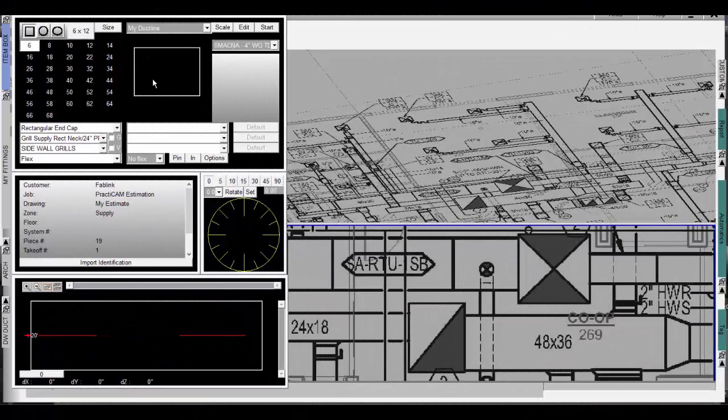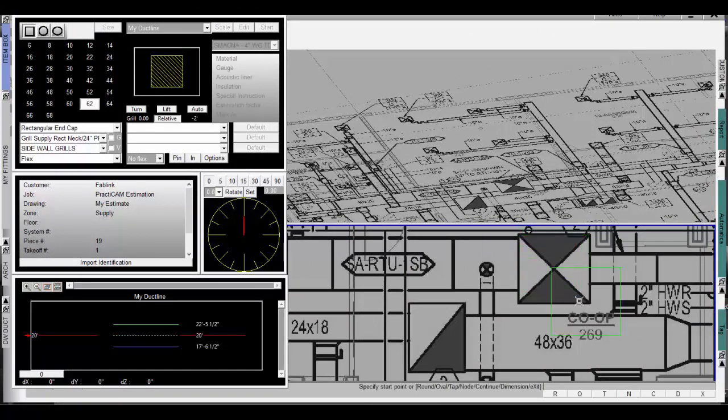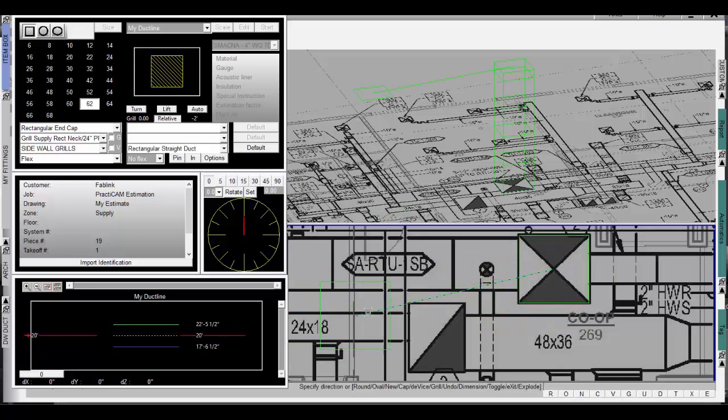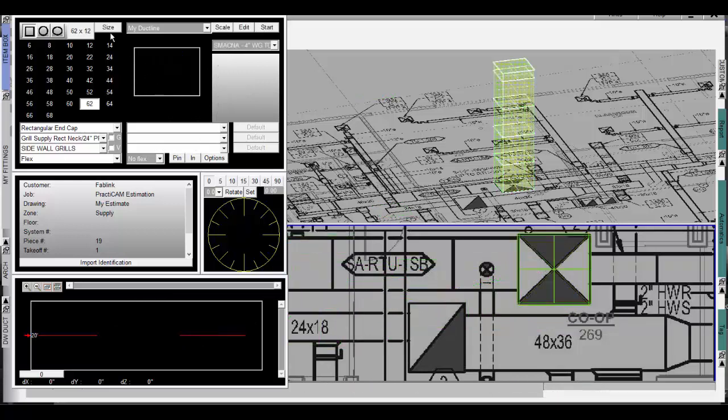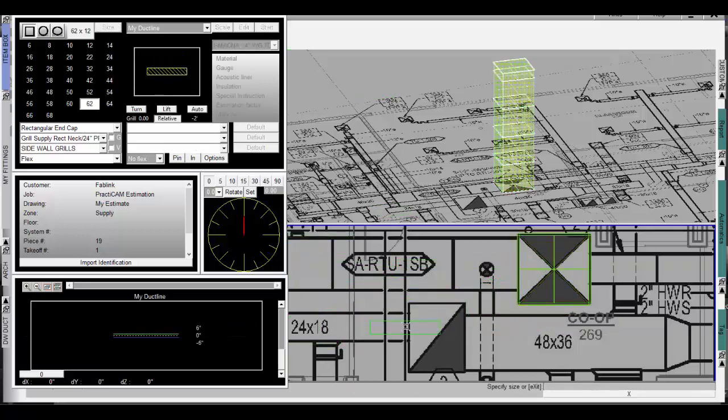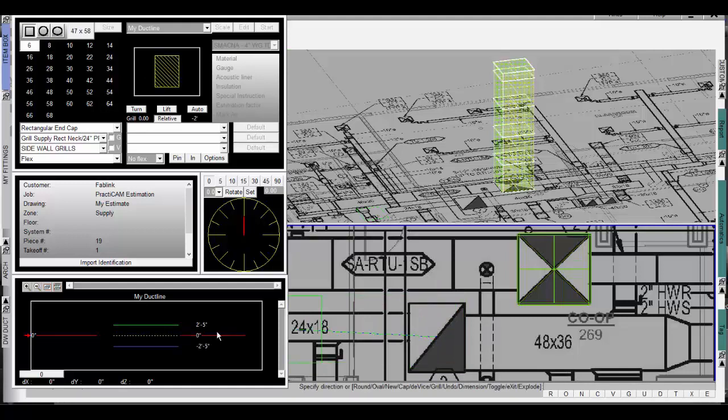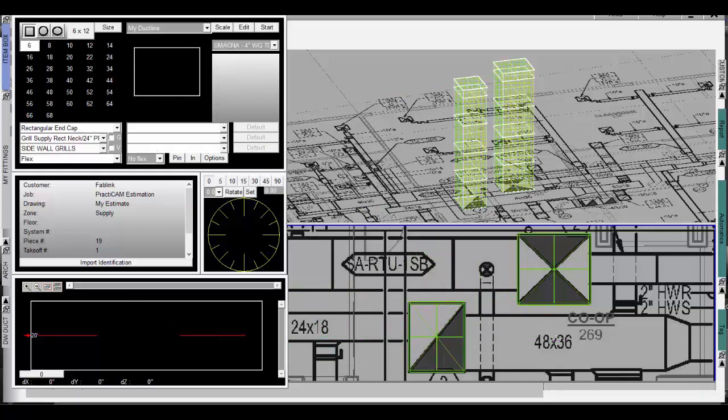The first thing we're going to show is how simple it is to draw elevated views accurately even while you're in plan view. See here as we draw a set of risers. First we choose the size tool which lets us click between two points to get the size of the riser we want to draw. Then we give the first elevation in the elevation box, click on the drawing, go back, give the second elevation, and the riser is drawn. In this example we drew everything from zero foot to 20 foot.